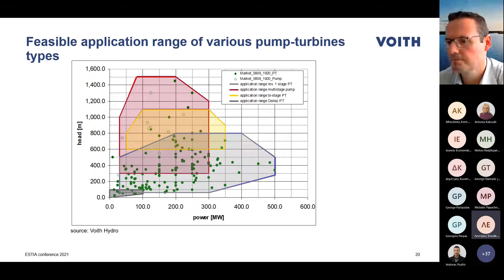Just an overview of the comparison of the ternary set, which I didn't explain before in detail. Actually, a ternary set is a motor generator connected to a separate turbine and a separate pump. This gives the advantage that you can cover bigger head ranges, and also, as shown below, some more details. Nowadays, when you look typically at the investment, you will use a system like on the right-hand side, where you have a conventional reversible pump turbine with a motor generator. The differences are shown below. Such a pump turbine would be, from the investment point of view, cheaper compared to a ternary set. Also, the space requirement is lower because you only have two components to be installed. On the other hand, you would have lower efficiency, and also have difficulties with the setting. Setting means the level of the pump below the lower tailwater level.